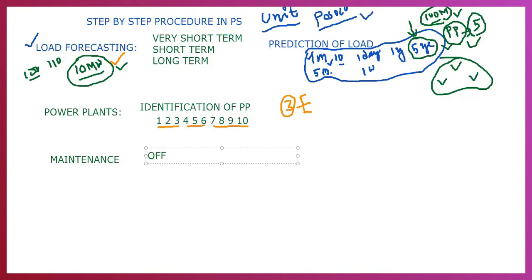This is because, as per legal requirements, every power plant has to be maintained. Any generator, turbine, boiler, superheater, chimney, or cooling tower has to be maintained every 1, 3, 4, or more years. For example, if the generator has to be maintained every 5 years, then after 5 years the generator has to be opened and everything has to be checked.